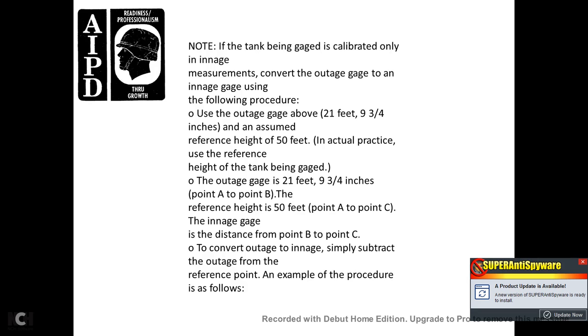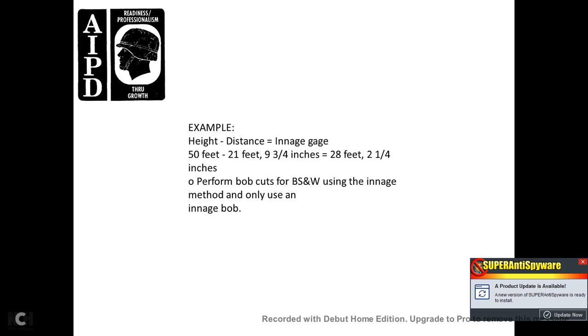45. The outage gauge from point A to point B is 21 feet 9 and three-quarter inches. The reference height from point A to point C is 50 feet. The innage is the distance between point B and point C. To convert the outage to innage, simply subtract the outage from the reference height. In the example: reference height 50 feet minus 21 feet 9 and three-quarter inches equals an innage of 28 feet 2 and one-quarter inches. Perform the bob cut — cuts of the bottom sediment and water using the innage method. Only use an innage bob.